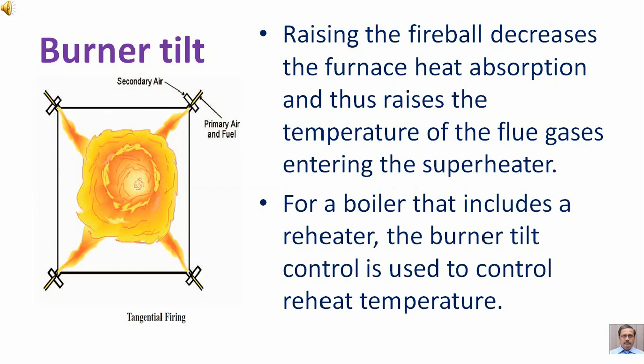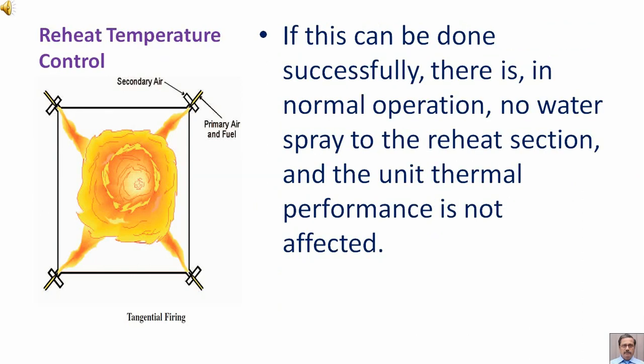For a boiler that includes a reheater, the burner tilt control is used to control reheat temperature. If this can be done successfully, there is in normal operation no water spray to the reheat section and the unit thermal performance is not affected.